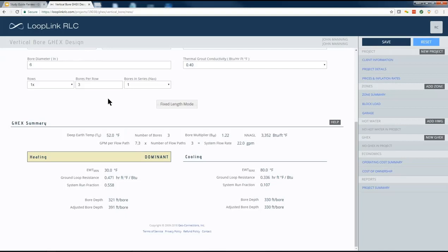So now notice I just bumped my bores per row to 3. So I've got a 1x3 bore field layout. So 3 bores total, 7.3 GPM per loop. And keep in mind that's when both of these heat pumps are running in the heating mode, which is what we're going to be most concerned about. So 7.3 is right in that sweet spot of 2 to 3 tons per loop in the field. Now you can see my adjusted bore depths are just under 400 feet the way that I've laid it out right now.